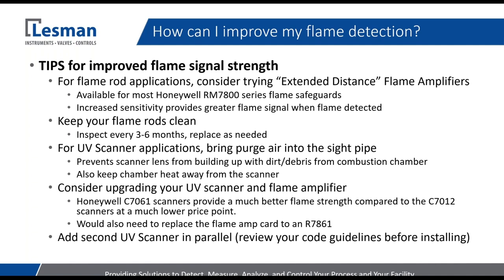The other thing you can do is periodic inspection of flame rods and keeping them clean. If you've got flame rods that could be fouling and building up soot, it may be good to inspect them every three to six months. Every application is different — if it's a dirtier application and your flame rod is more suspect to fouling, you may want to inspect more frequently. As they age, if the fouling isn't coming off or you start to see a decrease in your flame signal, you may just want to replace them. A good rule of thumb: every three to six months keep them clean, and then annually replace them.